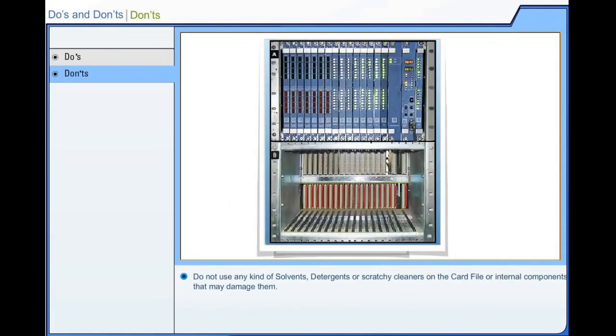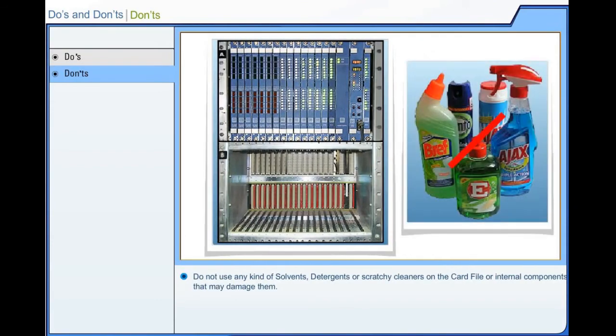Do not use any kind of solvents, detergents, or scratchy cleaners on the card file or internal components, as they may damage them. Also, do not use a vacuum cleaner or blower inside the card file, as that may cause damage to it.